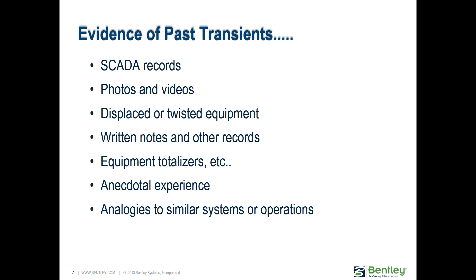When investigating transient problems, there are other things you can look at: SCADA records, photos of past transient damage, videos of pipes shaking, displaced equipment or twisted pipes from transient forces, written notes from the past, equipment totalizers, anecdotal experience from colleagues, or case studies analogous to similar systems. These are the types of things you might want to gather before doing a transient analysis.